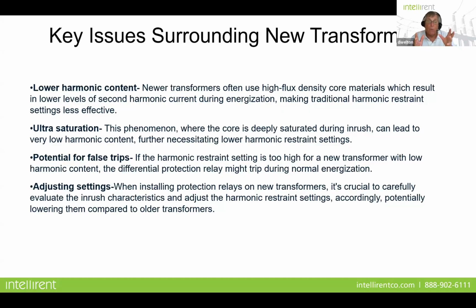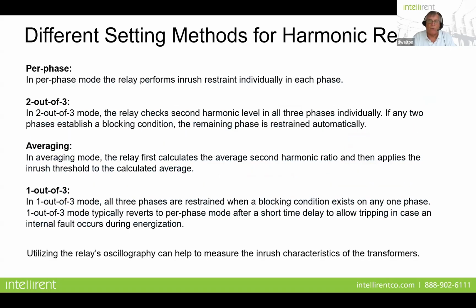And that means basically what we're seeing here is that the new materials in some of your core and shell form transformers are giving off much lower harmonics. And the reason I bring this up is that your traditional setting of 25% isn't going to be applicable anymore. You may have to go all the way down to 8 or 10 or 12%. How do you know what kind of harmonics you're going to see? Well, the best way is to energize the transformer, capture the waveform, and analyze it to see exactly how much harmonics is being generated during that inrush. And that will help you with your setting. Otherwise, if you just put it at 20%, you may see a nuisance trip.